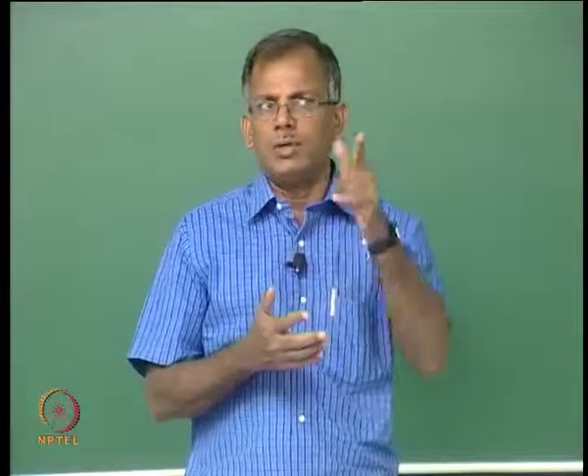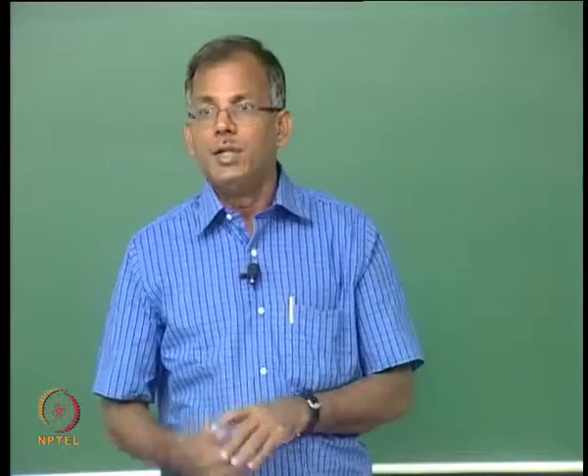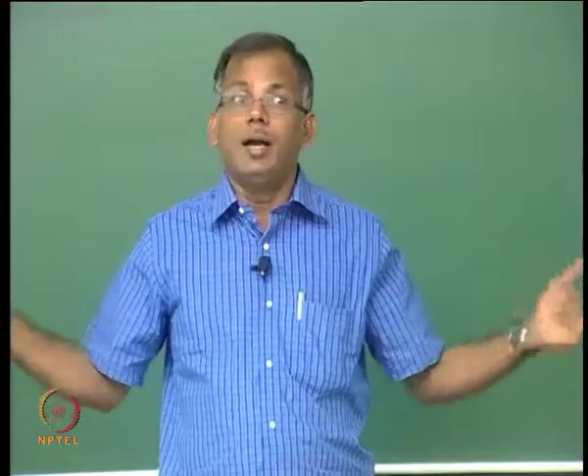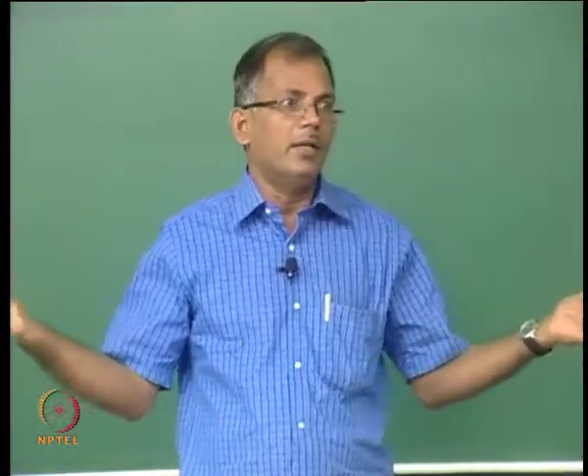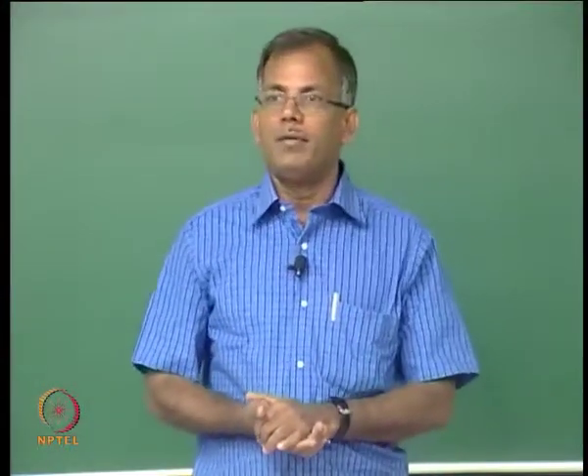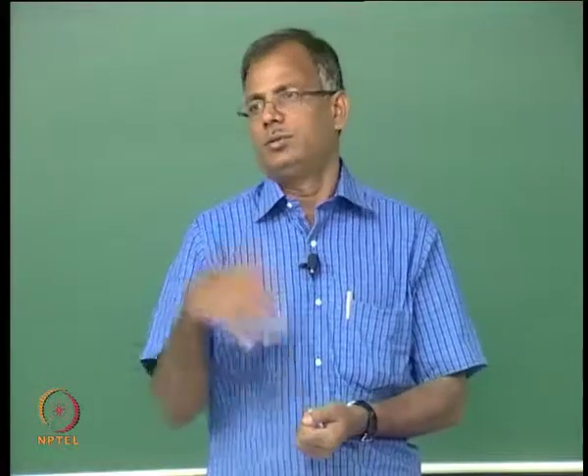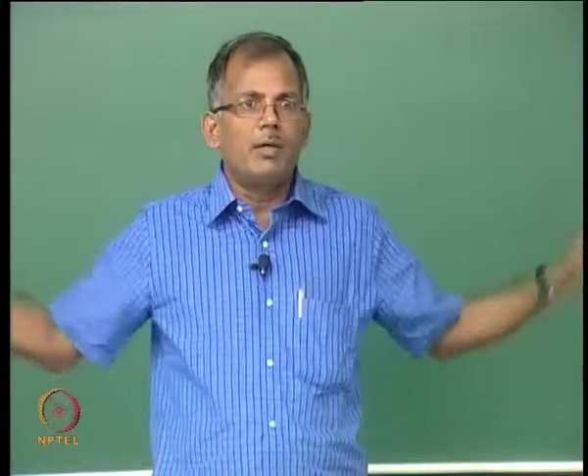The airlock needs to be pressurized — you keep the inside pressure higher than the outside so that ingress is not possible. Normally the outside is at atmospheric pressure, so you need to pressurize the inside slightly higher — not too high — so there is a potential for air to go out but not come in.